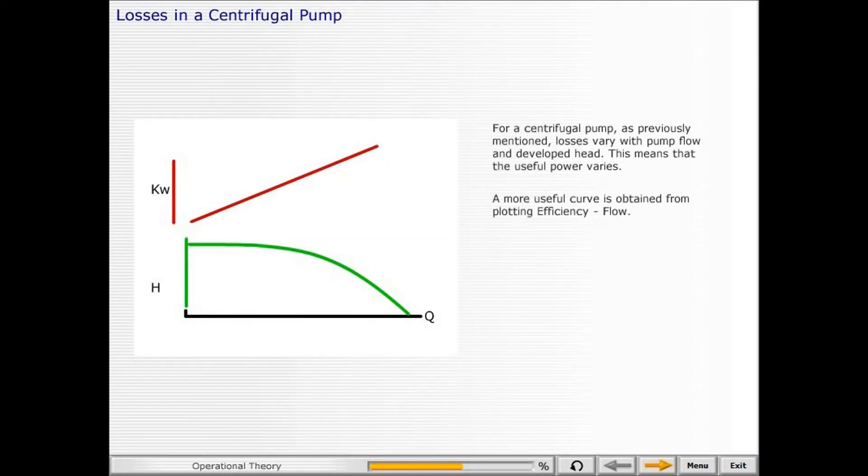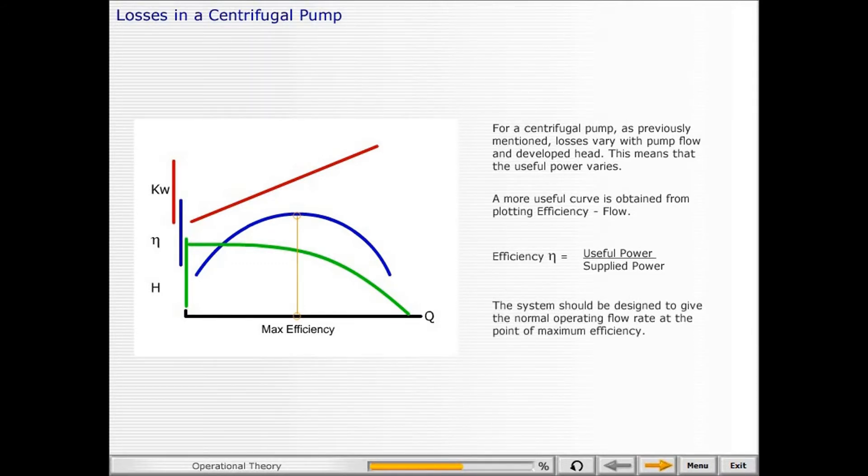For a centrifugal pump, losses vary with pump flow and developed head. This means that the useful power varies. A more useful curve is obtained from plotting efficiency to flow. Efficiency equals useful power divided by supplied power. The system should be designed to give the normal operating flow rate at the point of maximum efficiency.